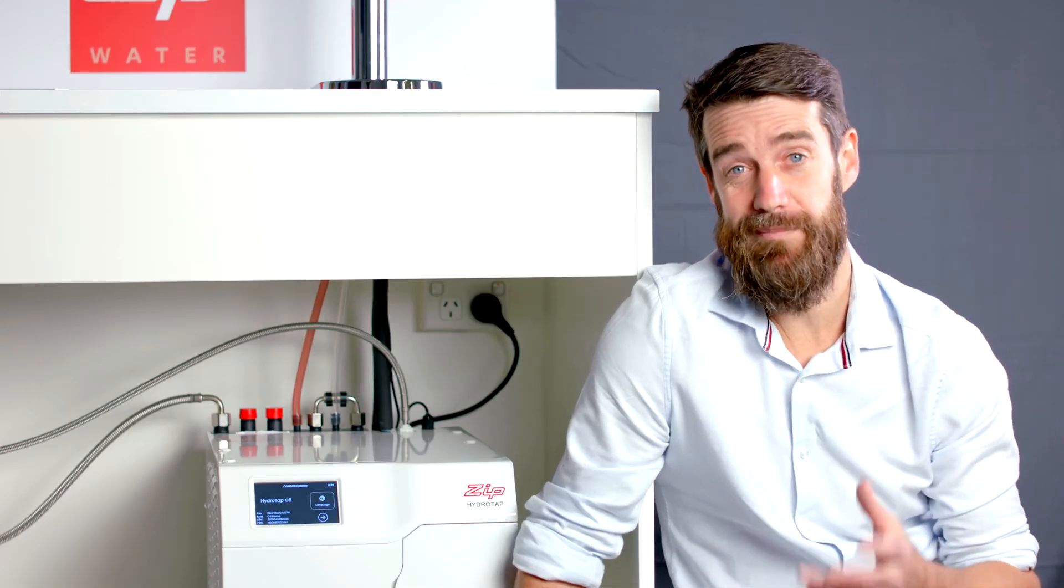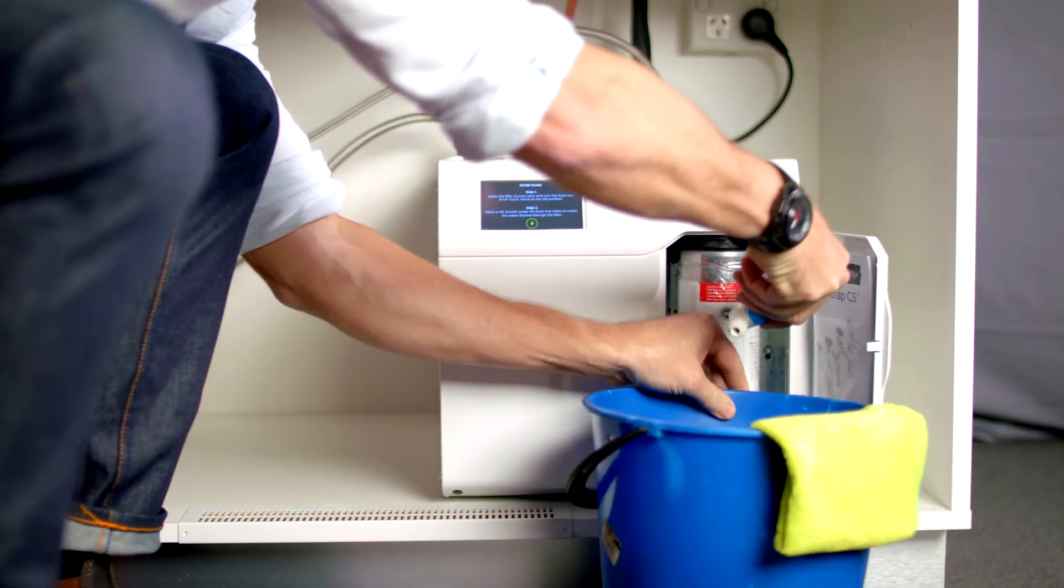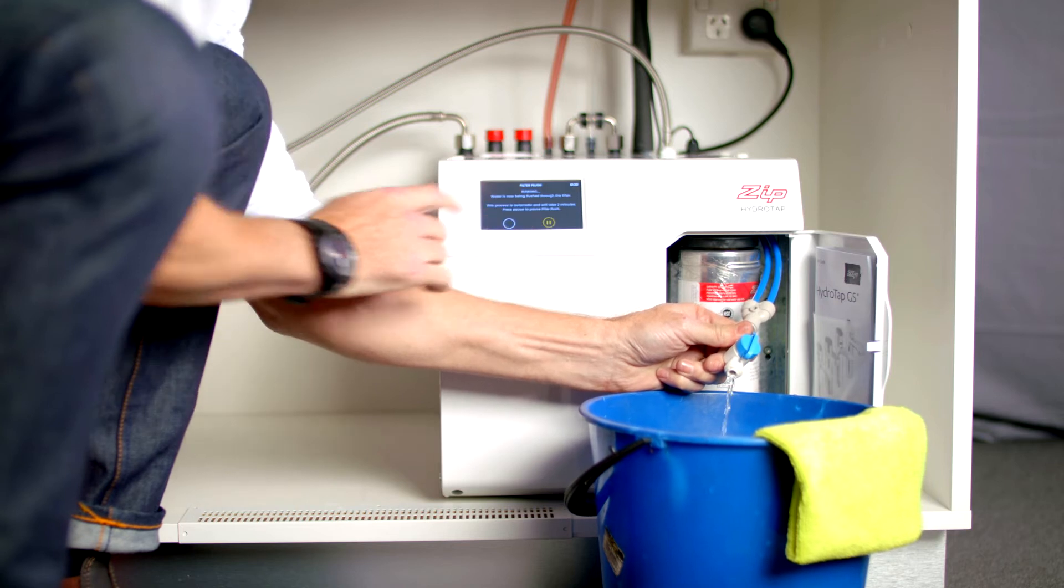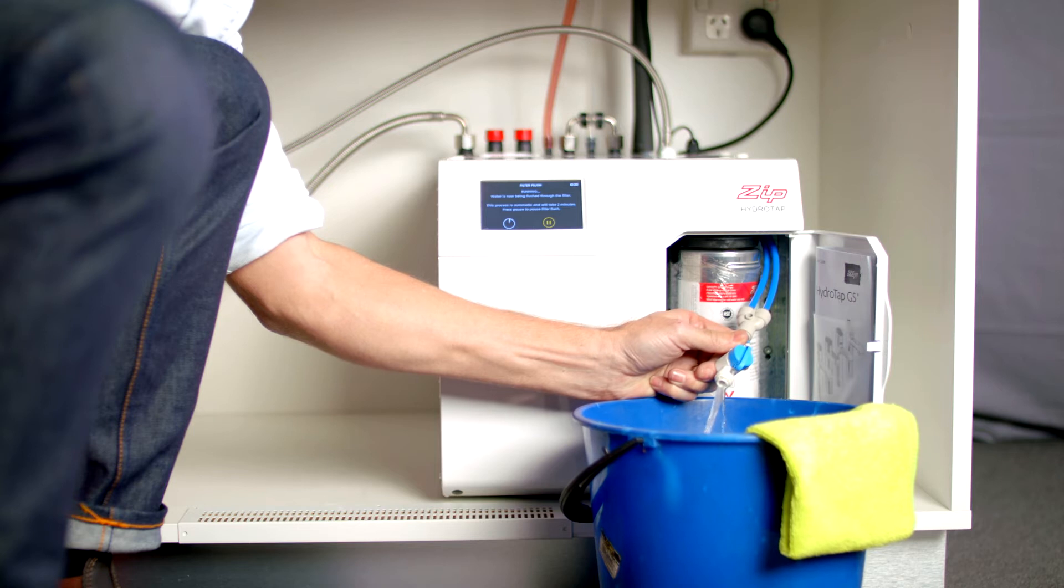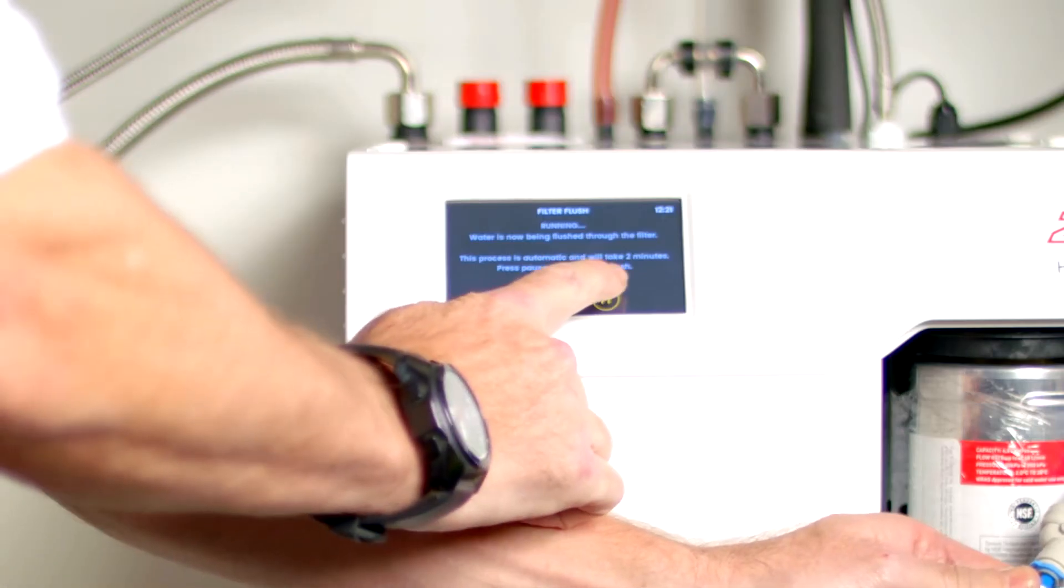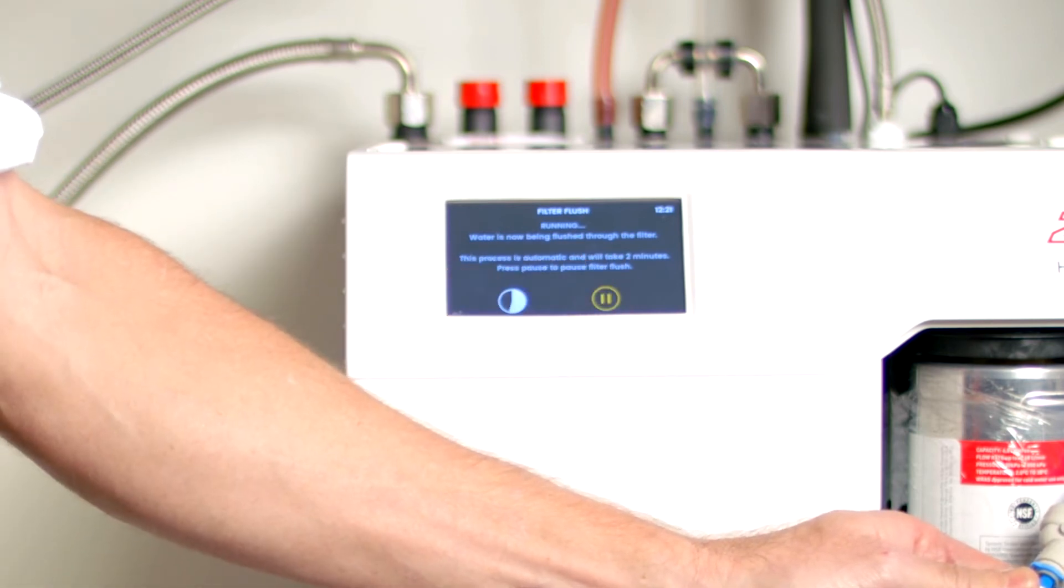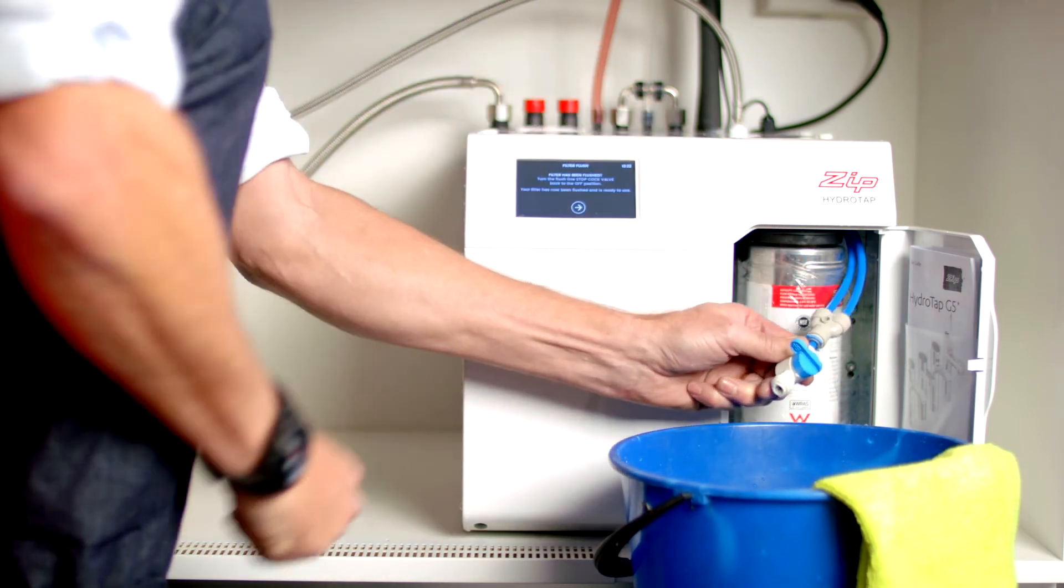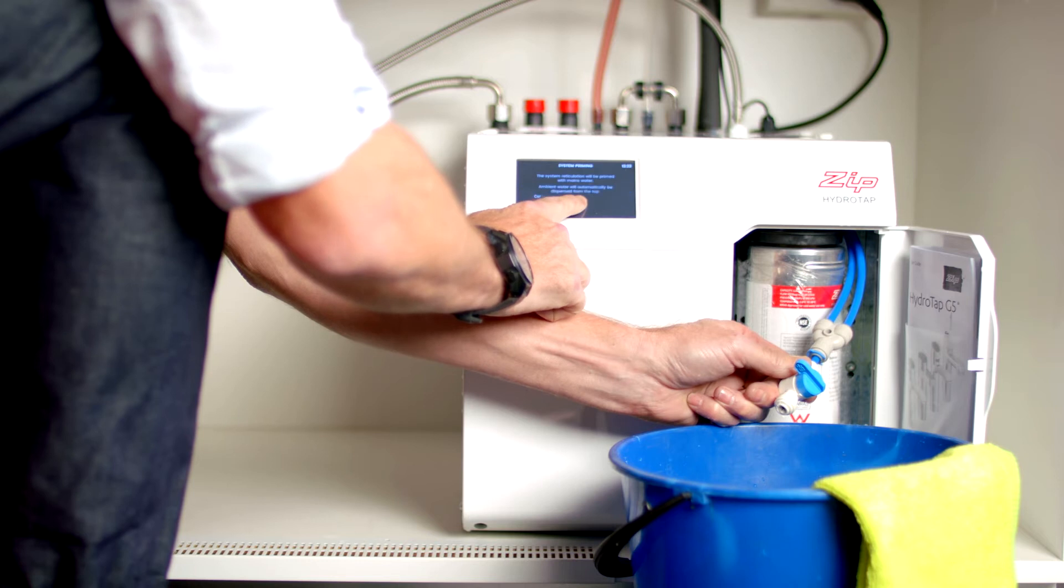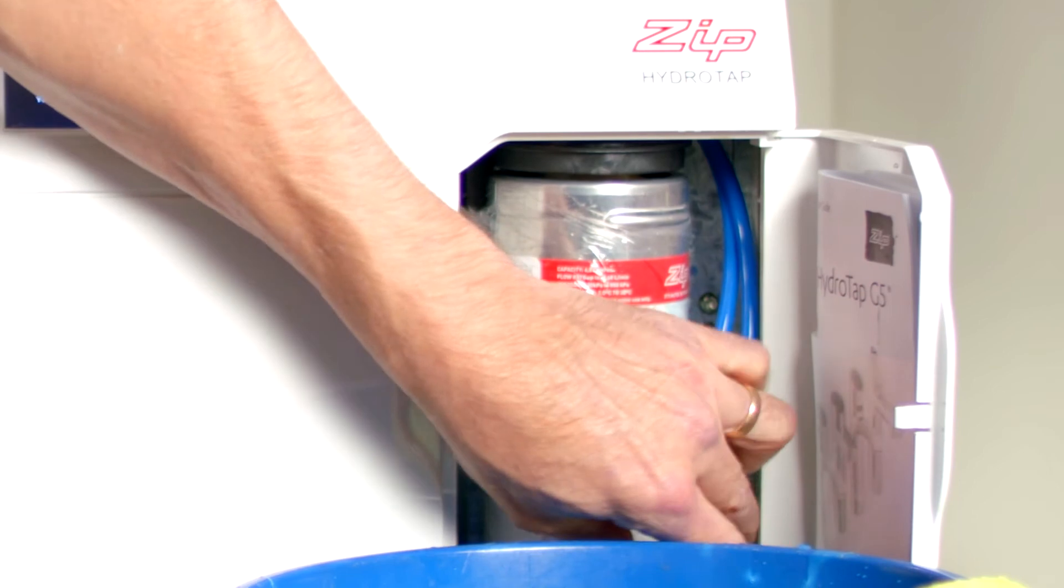Next the internal filter needs to be flushed. Using a bucket place the filter flush hose in the bucket and open the stopcock. Press the play button and the filter flush process will start. This process is timed to take two minutes. If you need to pause the filter flush press the pause button on the LCD. When you're ready to resume the filter flush press the play button. Once the filter flush has stopped turn the stopcock off and give it a shake. Press the arrow button to go to the next screen. Put the flush hose back in the filter compartment and close the filter door.